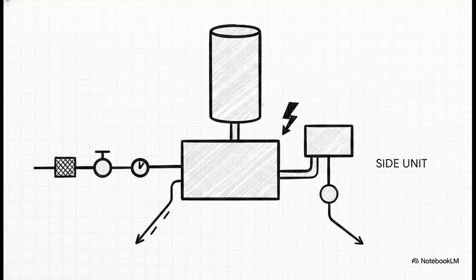Knocking out the mechanical requirements, you've got to be pretty precise. For the main water supplied to the branch controller, you're going to need a strainer, a shutoff valve, and a pressure-reducing valve. Now, since we are heating water, an expansion tank is completely non-negotiable, and this is absolutely crucial. It must be mounted at or above the height of the hybrid controller. Electrically, you're looking at 208 to 230 voltage power across the board for the controller, the outdoor unit, and the fan coils. Oh, and don't forget your drain lines. You might even need internal condensate pumps to lift the liquid up and out to the main line, especially if you're using those wall-mounted units.